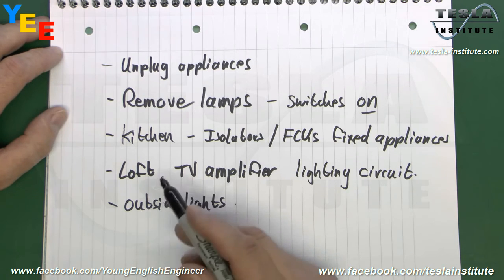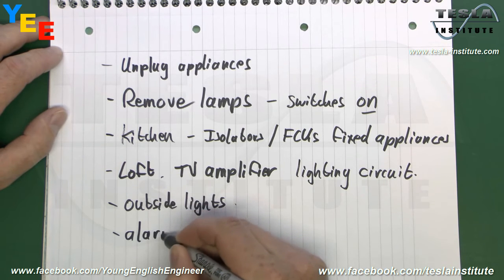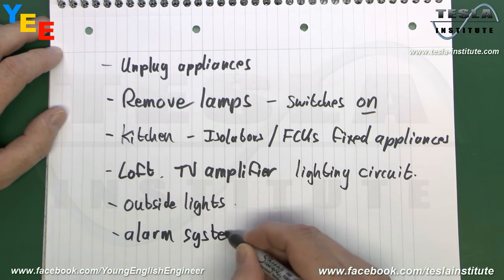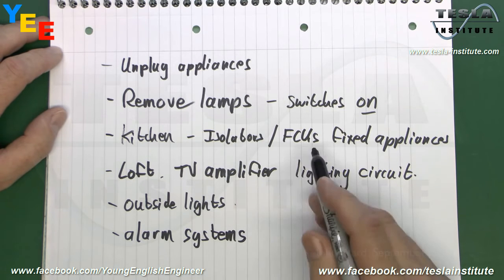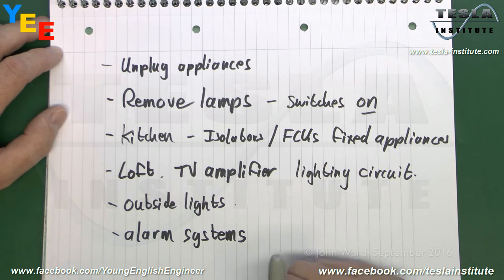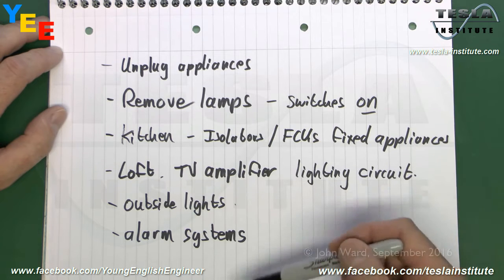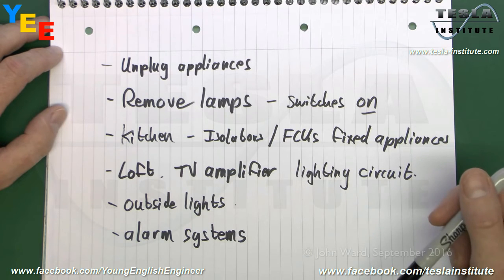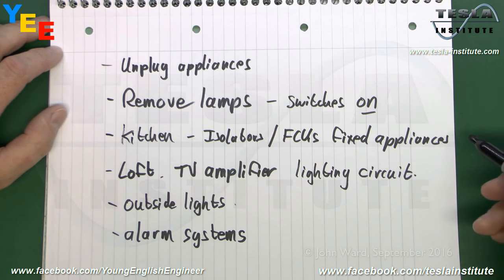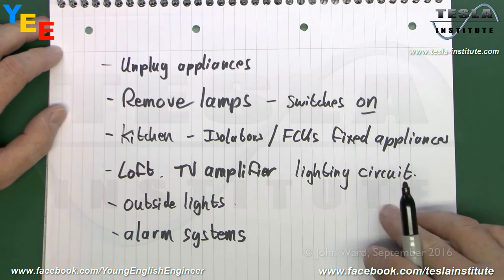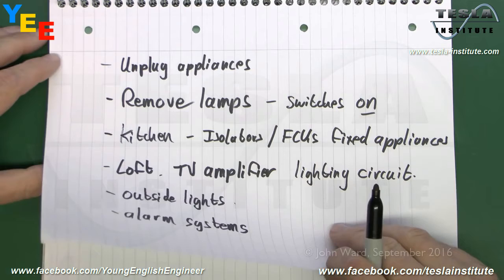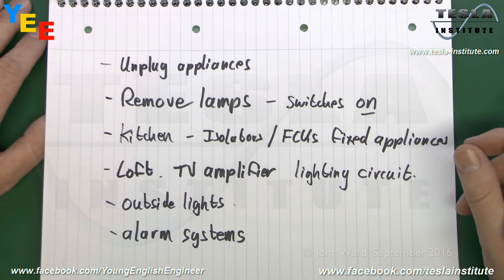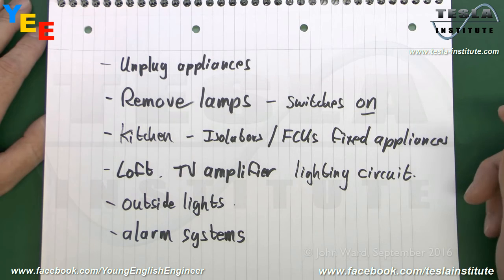And again, quite often in the loft or in cupboards and things, you may find alarm systems, which by their nature don't generally have a switch. And again, they should have some kind of fuse or something which you can remove to actually isolate them from the circuit. And there's quite a lot of other stuff as well, but be aware that some of these more non-obvious things quite often do exist, so it's really worthwhile having a look in the loft and any sort of cupboards and other places where equipment may be installed. Now, once you've removed all those, it's a question of just attaching the piece of test equipment to the various wires, pressing the button and recording the result. And of course you would repeat this for each of the individual circuits.